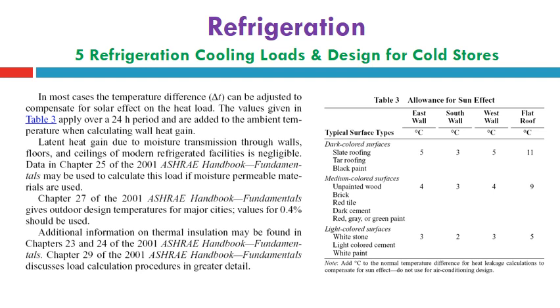Chapter 27 of the 2001 ASHRAE Handbook Fundamentals gives outdoor design temperatures for major cities. Values of 0.4 percent should be used for the refrigerated space. This chapter can also be used to consider the outside design temperature in HVAC applications, in air conditioning systems. But for refrigerated space, we can take the values of 0.4 percent as a selected value from the values shown in this chapter 27.